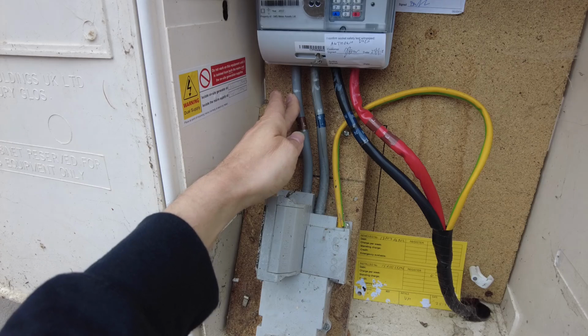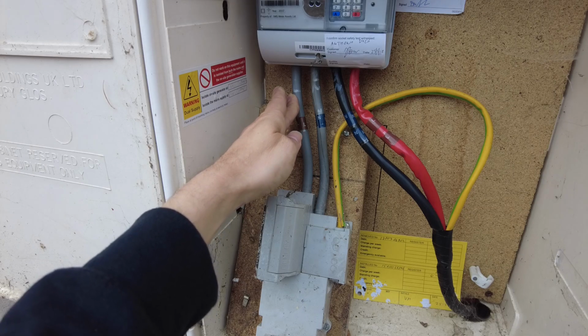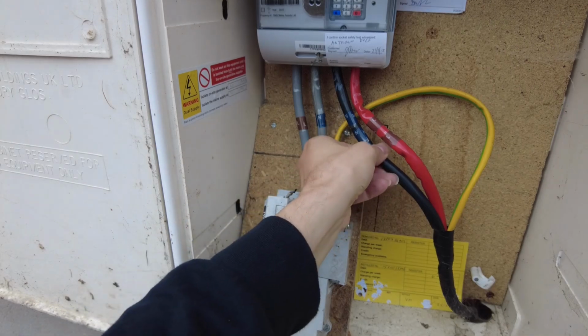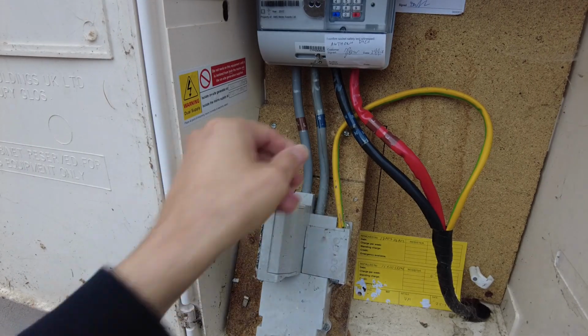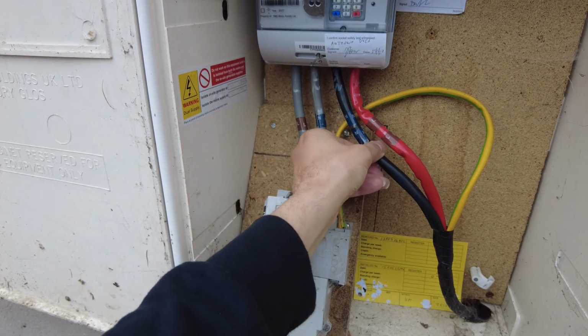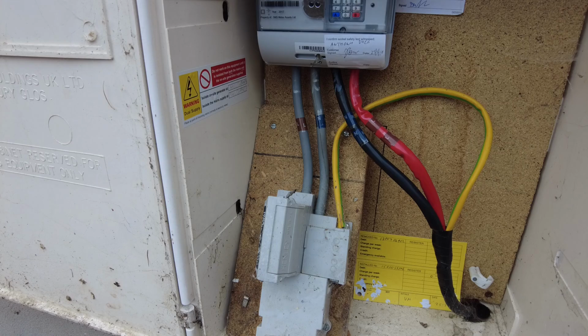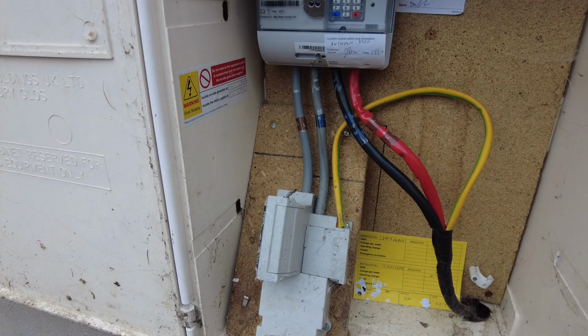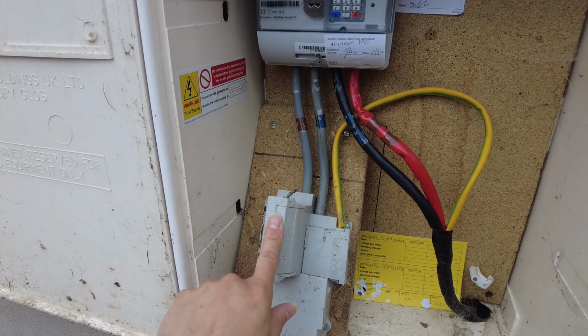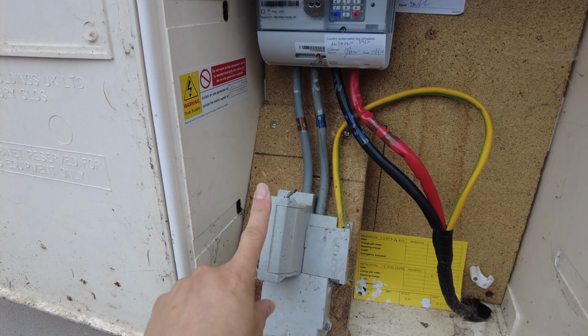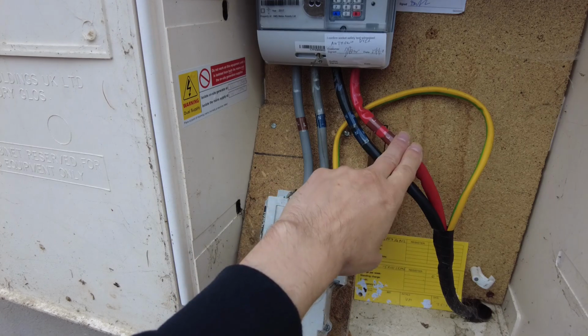That is more than adequate for 100 amp current carrying capacity. But these cables here are only 16 square millimeters. There's no slack in here, but there's quite a bit of air in there. And my electrician tells me that 16 square millimeters is indeed the case. Now, according to wiring regulations, the rating of this cable when it's clipped to a wall, which is known as clipped direct in wiring regulation terms, is only 87 amps. So I don't think there's a 100 amp fuse in here. 80 amps is certainly feasible, but judging from electricians' forums, 60 amps is also quite common for 16 square millimeter cable.